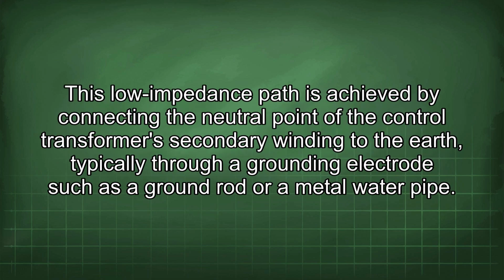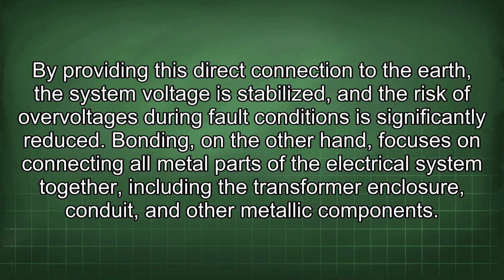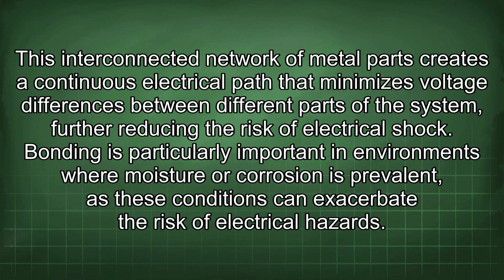This low impedance path is achieved by connecting the neutral point of the control transformer secondary winding to the earth, typically through a grounding electrode such as a ground rod or a metal water pipe. By providing this direct connection to the earth, the system voltage is stabilized, and the risk of overvoltages during fault conditions is significantly reduced. Bonding, on the other hand, focuses on connecting all metal parts of the electrical system together, including the transformer enclosure, conduit, and other metallic components. This interconnected network of metal parts creates a continuous electrical path that minimizes voltage differences between different parts of the system, further reducing the risk of electrical shock.